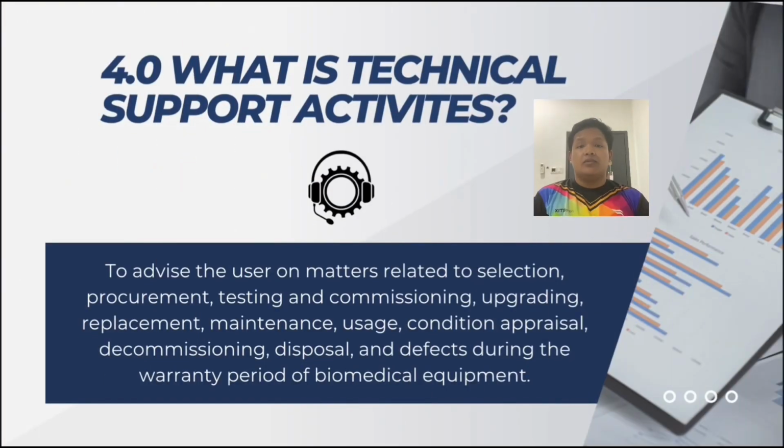Next one is, what are technical support activities? It is to advise the user on matters related to selection, procurement, testing and commissioning, upgrading, replacement, maintenance, usage, condition appraisal, decommissioning, and disposal, and also defects during the warranty period of biomedical equipment.